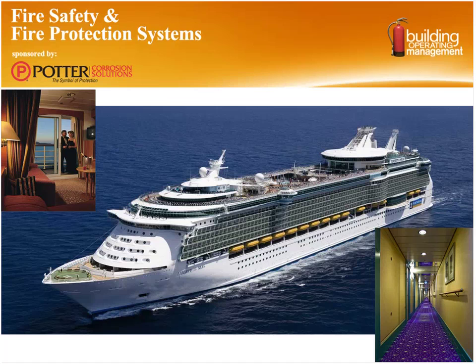So where have we seen systems like this? You may have seen one if you've ever been on a cruise. The cruise ship industry was one of the first to take on these systems. If you think about what a cruise ship is and what it's really trying to be, it's a floating hotel. And you'd have to look really close to know that this was a fine water mist system, but the reality is those sprinkler heads that you see in your rooms or in the hallways or other public areas probably wouldn't look a lot different to the typical person than a normal sprinkler head would.